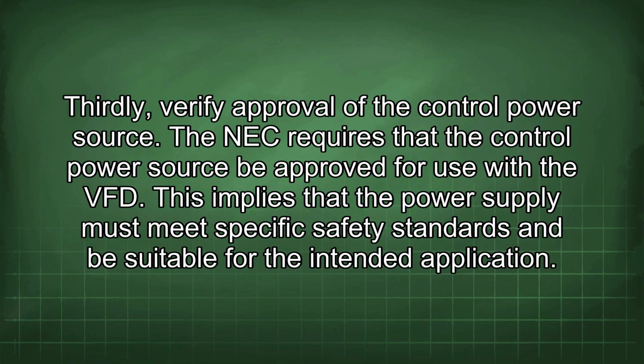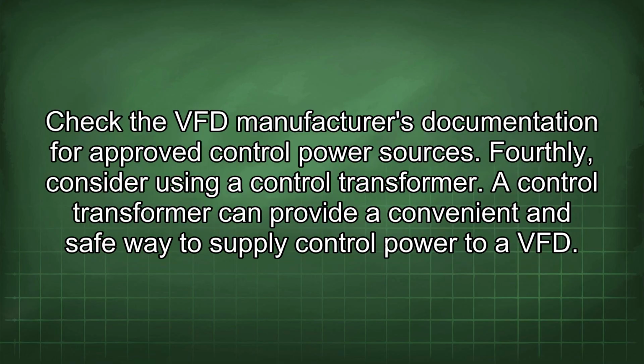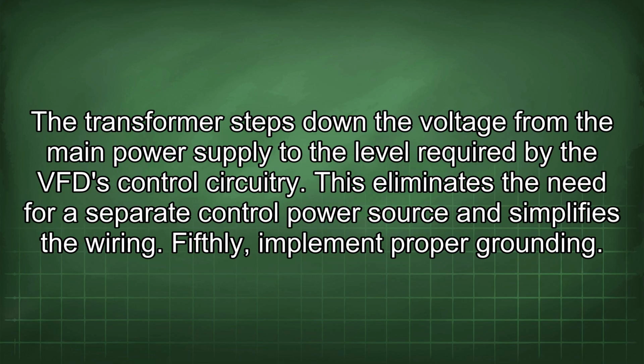Thirdly, verify approval of the control power source. The NEC requires that the control power source be approved for use with the VFD. This implies that the power supply must meet specific safety standards and be suitable for the intended application. Check the VFD manufacturer's documentation for approved control power sources. Fourthly, consider using a control transformer. A control transformer can provide a convenient and safe way to supply control power to a VFD. The transformer steps down the voltage from the main power supply to the level required by the VFD control circuitry. This eliminates the need for a separate control power source and simplifies the wiring.